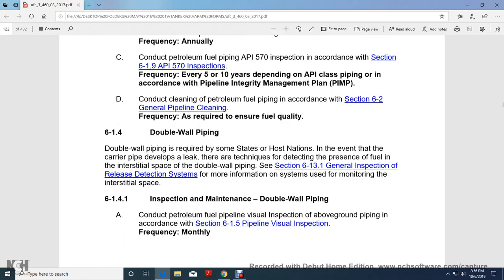to ensure fuel quality. 6.14, Double wall piping. Double wall piping is required to contain the fuel in the event that the carrier pipe develops a leak, with a technique for detecting the presence of fuel in the interstitial space of the dual wall piping. Section 6.13.1, General Inspection of the leak detection system, covers the use of the system for monitoring the interstitial space.